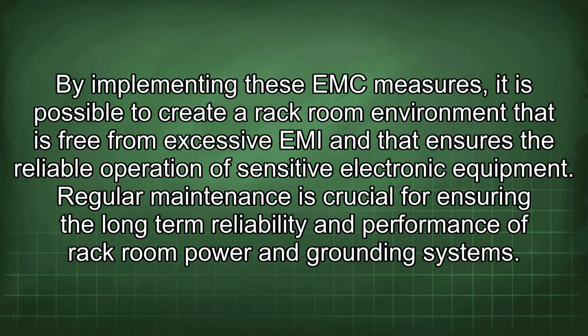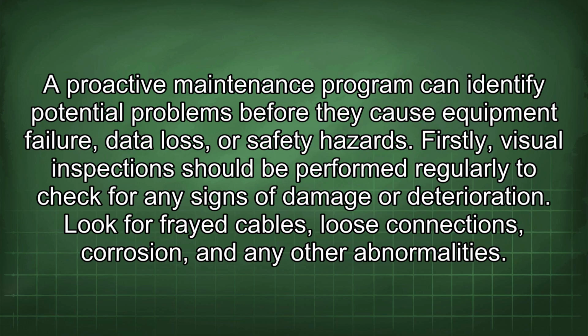Regular maintenance is crucial for ensuring the long-term reliability and performance of rack room power and grounding systems. A proactive maintenance program can identify potential problems before they cause equipment failure, data loss, or safety hazards. Firstly, visual inspections should be performed regularly to check for any signs of damage or deterioration. Look for frayed cables, loose connections, corrosion, and any other abnormalities.